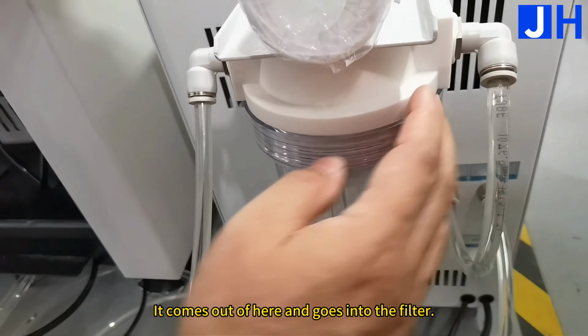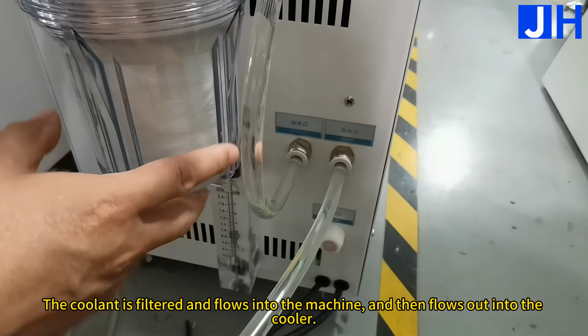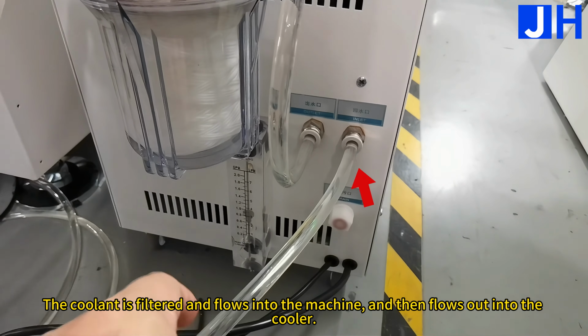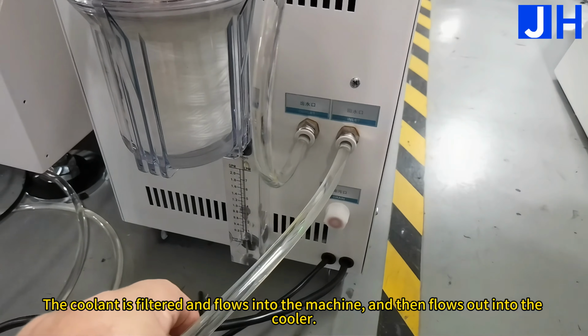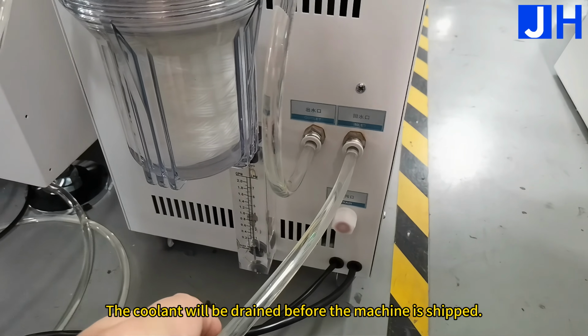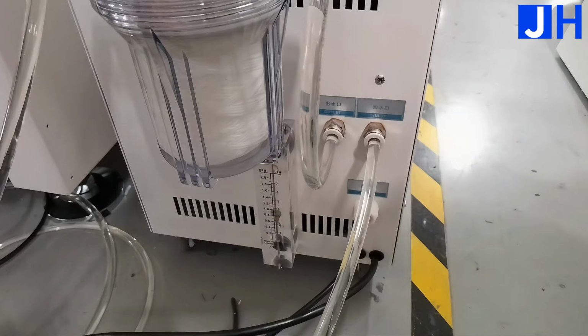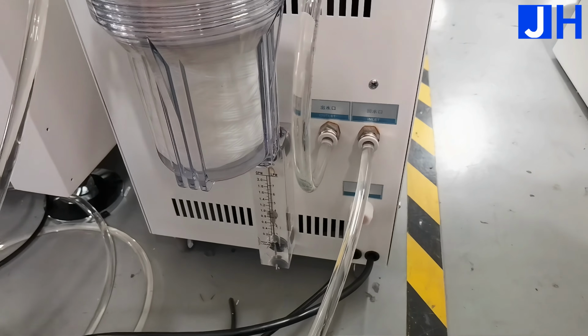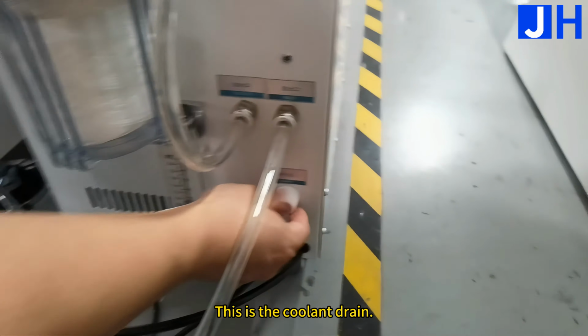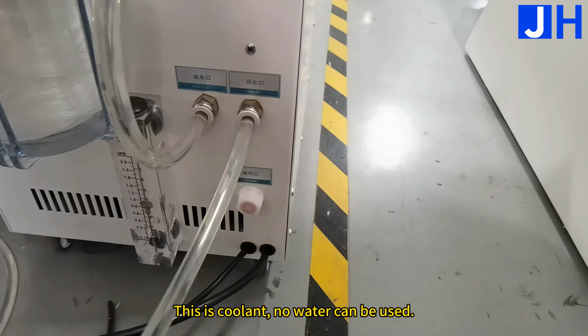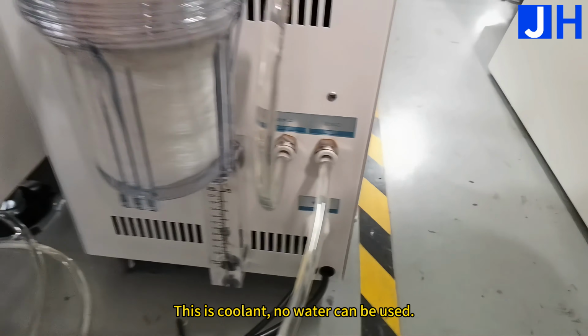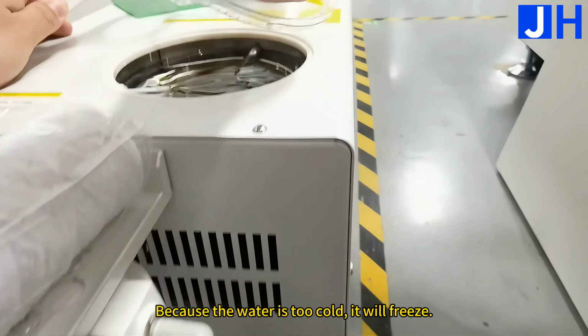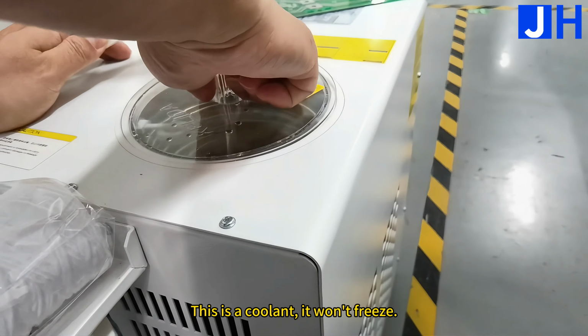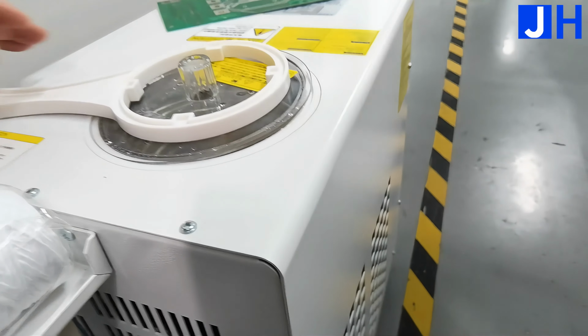This is the drain port. It comes out of here and goes into the filter. The coolant is filtered and flows into the machine, and then flows out into the cooler. The coolant will be drained before the machine is shipped. This is the coolant drain. This is coolant. No water can be used, because water will freeze when it is too cold. This is a coolant, it won't freeze.